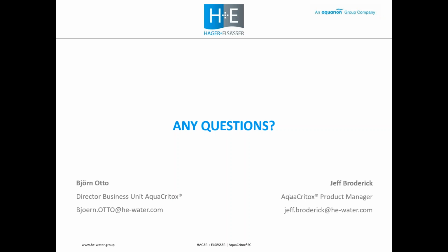So what we would do is we would take treated spent caustic from downstream of the package, and we would use that to then dilute the feed to allow us to reduce the COD concentration to within the allowable limit of the package. So when we have an understanding of your application, we can advise you on dilutions, or if necessary, allowable flow rates through the package. So we would tune our system to your application.